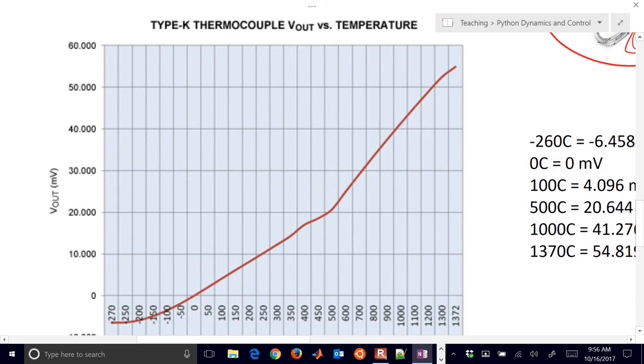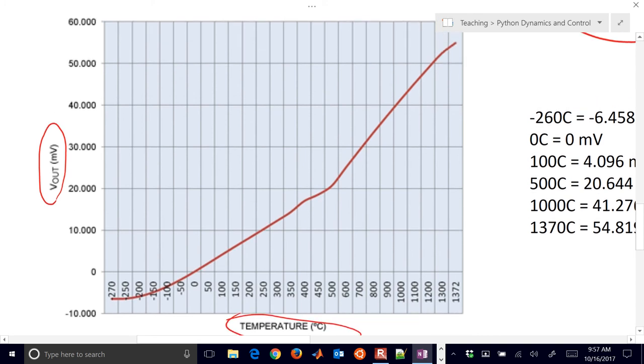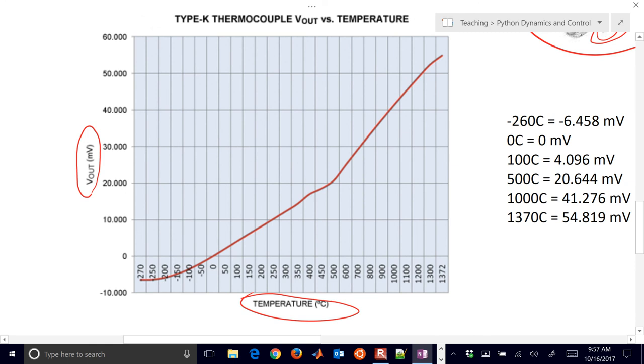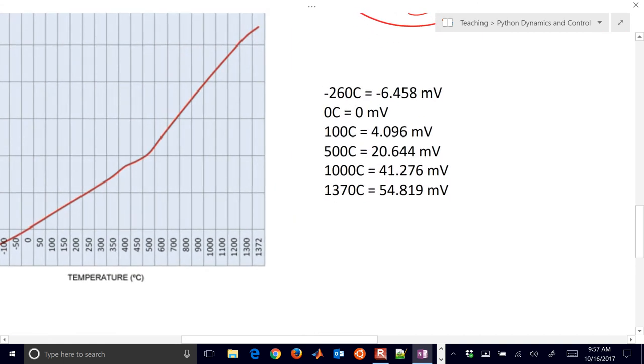Here's the voltage. The voltage versus the temperature down here at the bottom. Now, you can see this one is not necessarily a linear correlation. Now, it might be if you had something kind of in this region right here, that might be approximated really well by a linear function. And then you might have another linear function that kind of approximates it in that region. And then maybe a couple more that are approximated in those regions as well. Or you can have a signal conditioner where you'll just load in the calibration data. And we'll just do a linear interpolation or other method between some of those points. But there's, here's just some data that you might load in for the linear correlation, for example.